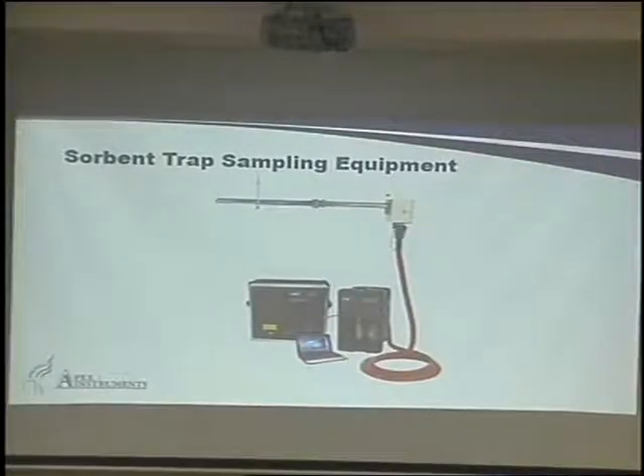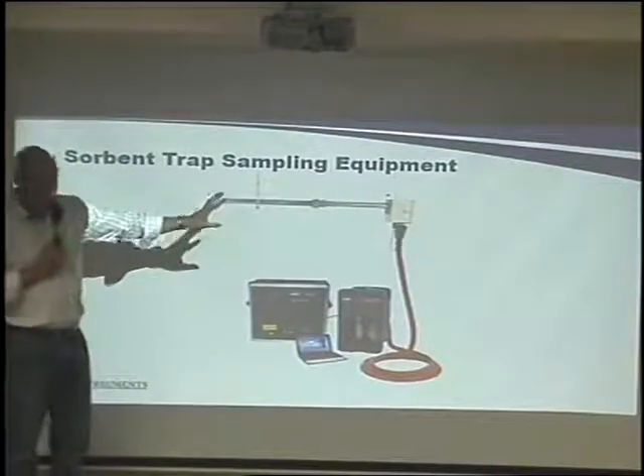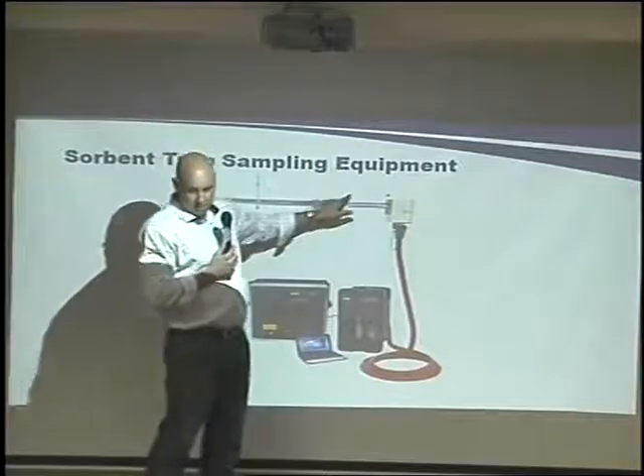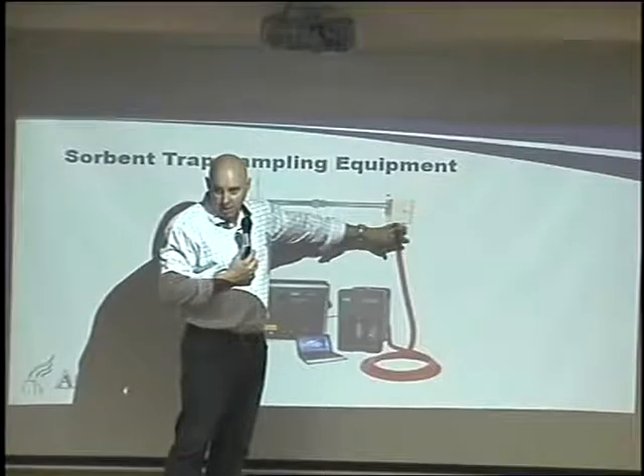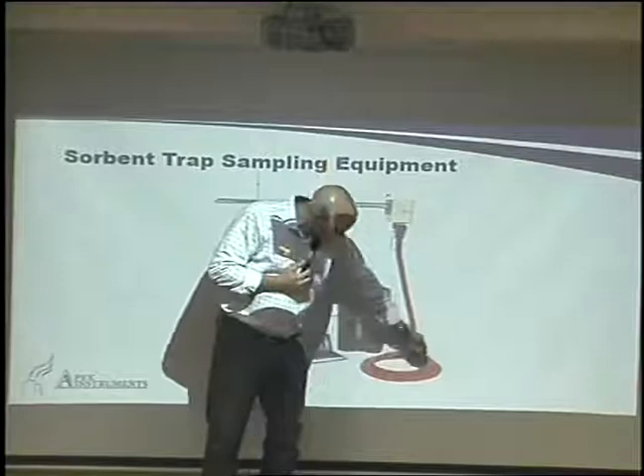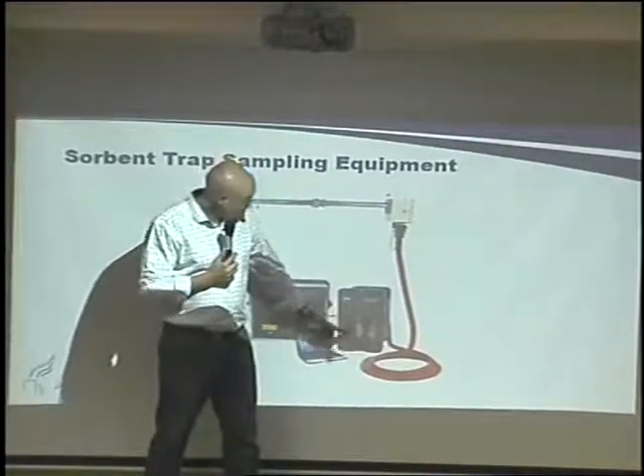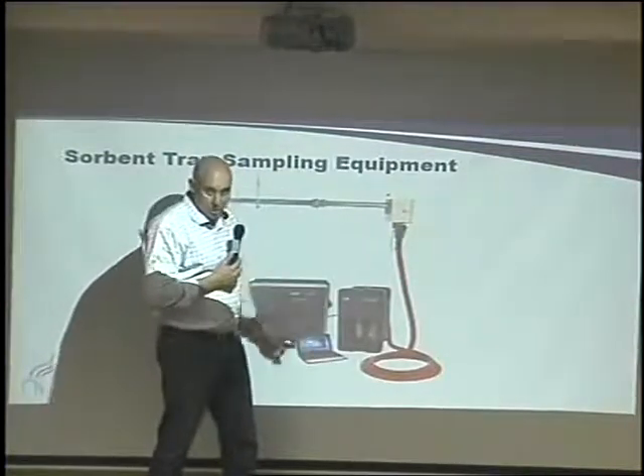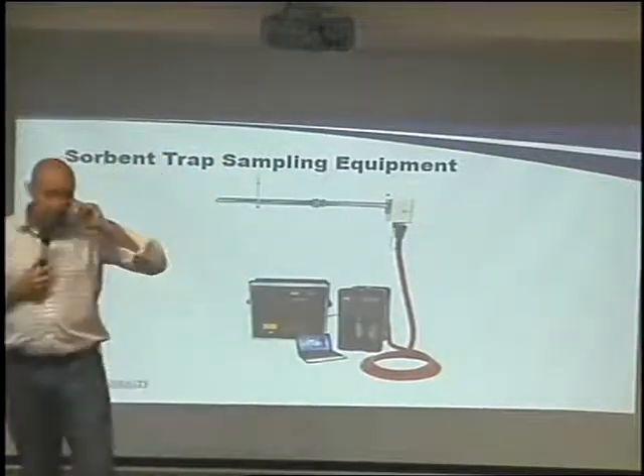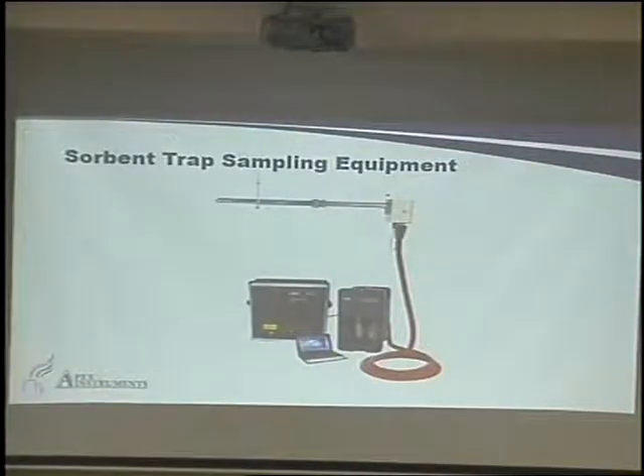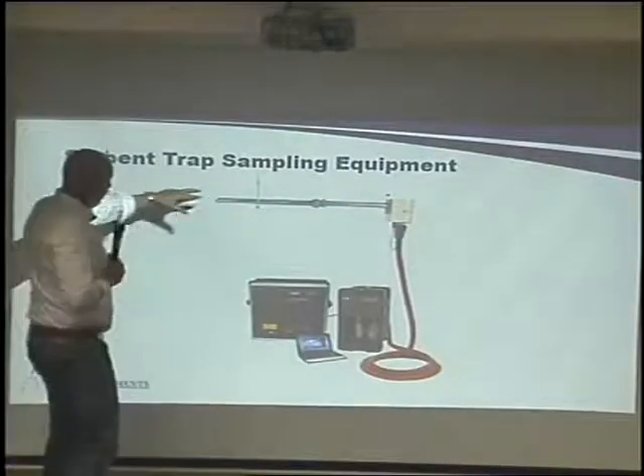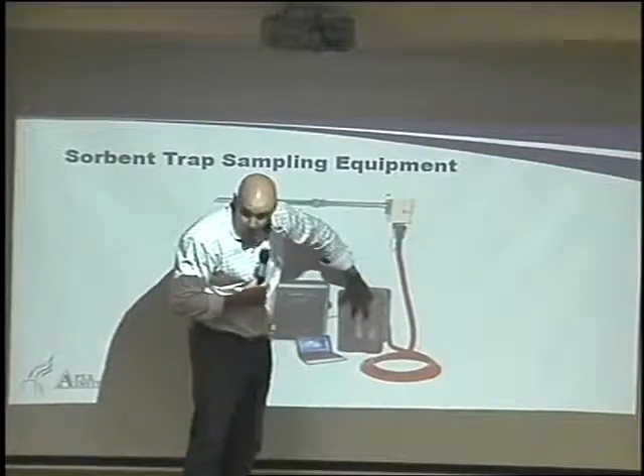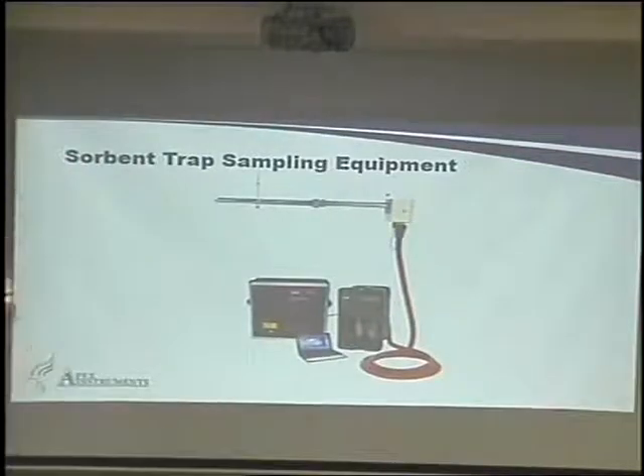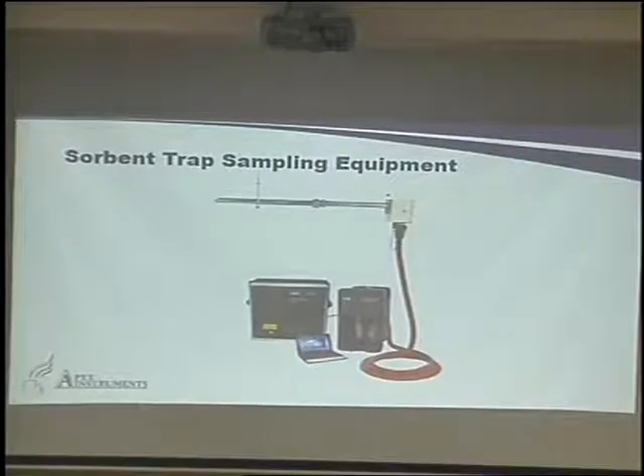So this is a picture here of our 30B system. I'll show you a close-up picture here soon, but the traps are in the front here. Heated probe, heated junction box to connect our umbilical. This is all kept hot and heated till we get to our chiller where we remove the moisture. Then we take a clean and dry sample to our console. And within this complete system, basically we have two independent systems, A side and B side, okay? So there's two traps, two sample lines, two knockouts, two gas meters, all combined in one system, okay? And then after we've done sampling, we're going to compare A and B to make sure they match, like a correlation, like we talked about before, okay?